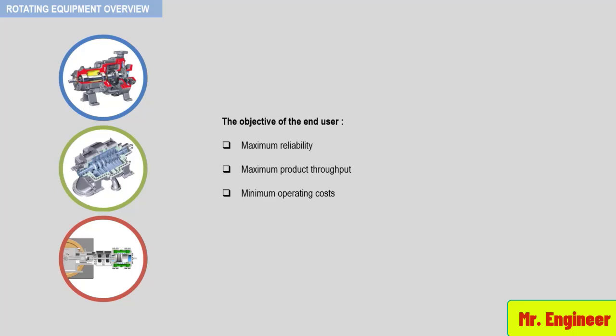In order to achieve these objectives, you must play a significant part in the project during the specification and design phase, and not only after the installation of the equipment in the field. Effective field maintenance starts with the specification phase of a project. Inadequate specifications in terms of equipment operating conditions, mechanical design, instrumentation, and the location of instrumentation will reduce equipment availability.